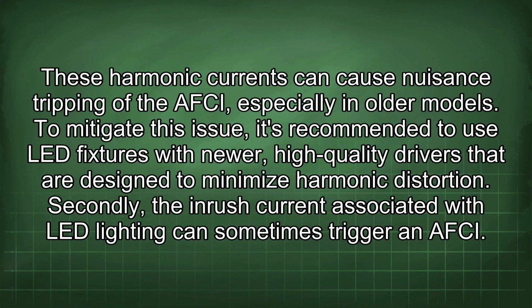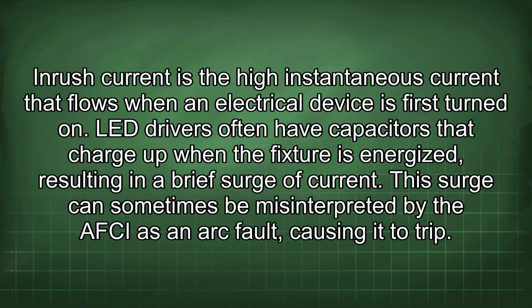To mitigate this issue, it's recommended to use LED fixtures with newer, high-quality drivers that are designed to minimize harmonic distortion. Secondly, the inrush current associated with LED lighting can sometimes trigger an AFCI. Inrush current is the high instantaneous current that flows when an electrical device is first turned on.